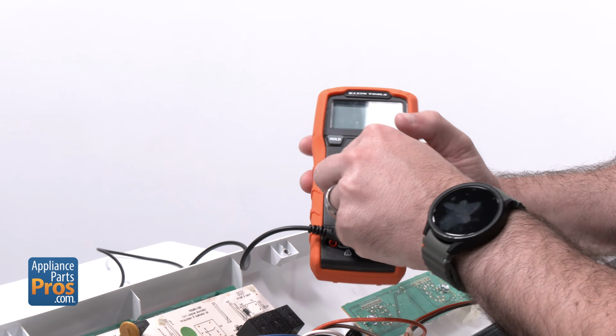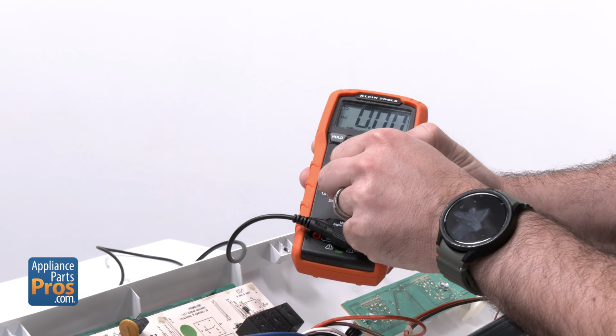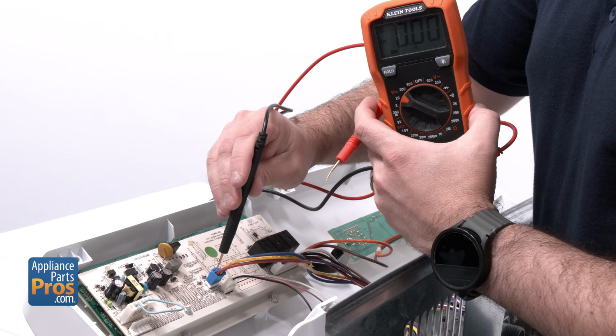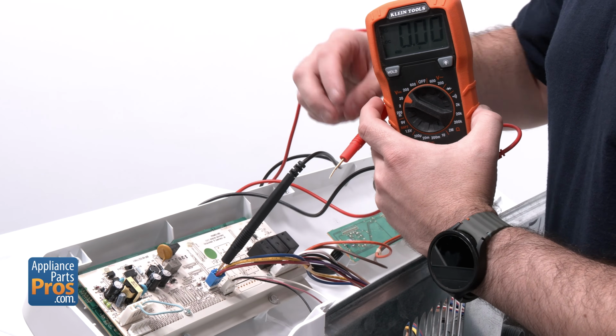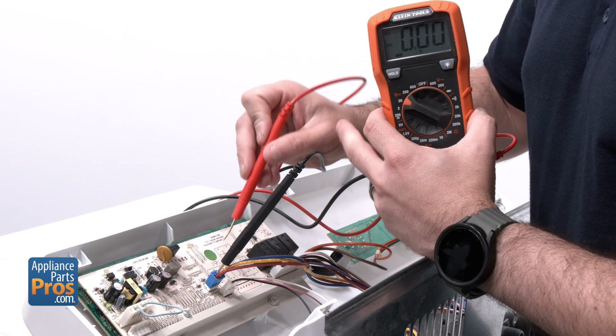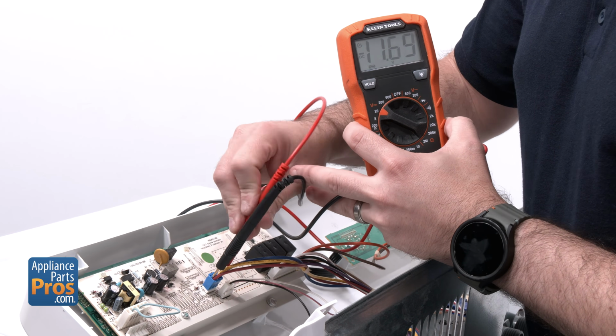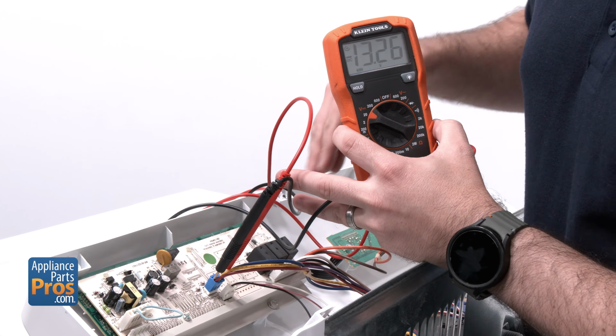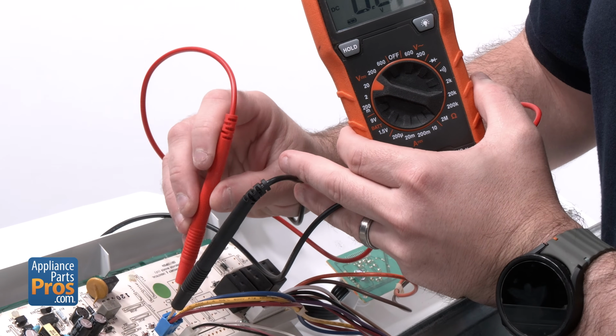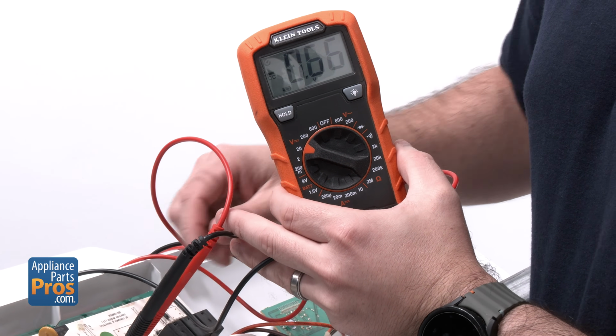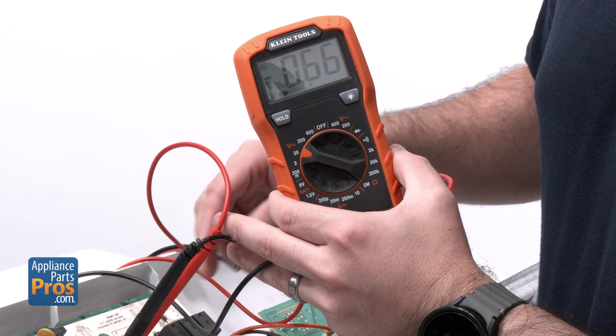Set your meter to volts DC. This is indicated by a V with a dotted or dashed line. Place the black meter probe on the red wire connector J7 and leave it there. Touch the red probe to the blue wire. You should see 12.8 volts DC. Next, move the red probe to the yellow wire. You should see a pulsing voltage. If either voltage is missing, the main control has failed. If both are present, stop the cycle and continue troubleshooting.